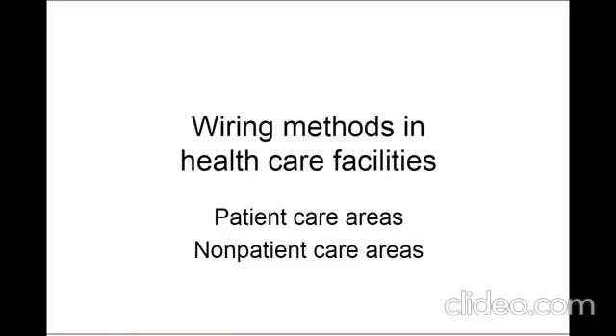Article 517 contains stricter wiring method requirements for patient care areas and not only ensures adequate and reliable power is available to treat a patient, but also helps prevent shocks. Patients may be in direct contact with electromedical devices, and it is important to minimize voltage potential between conductive surfaces likely to become energized and conductive surfaces that may be in contact with the patient.